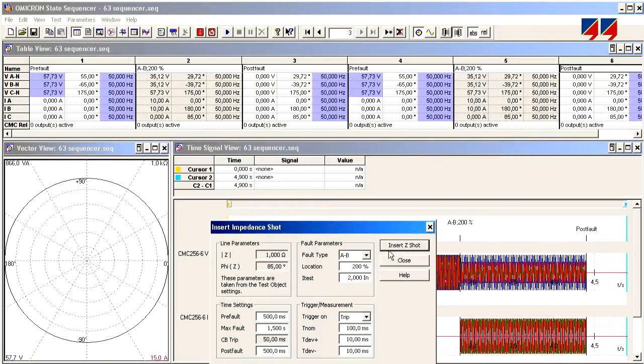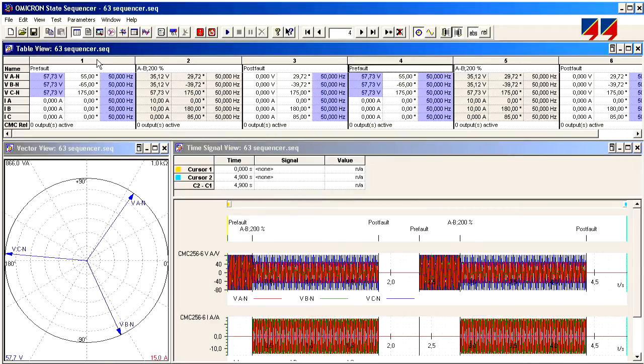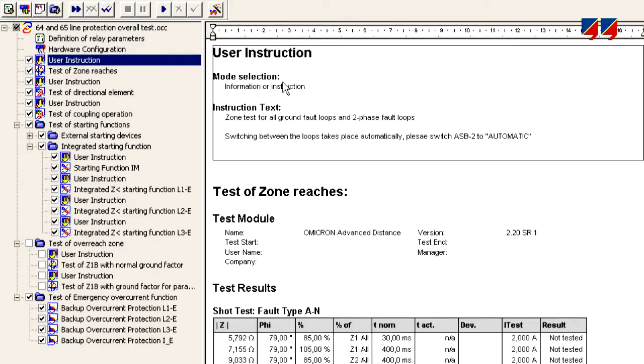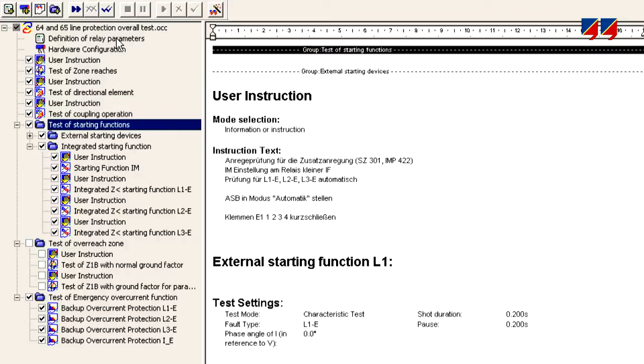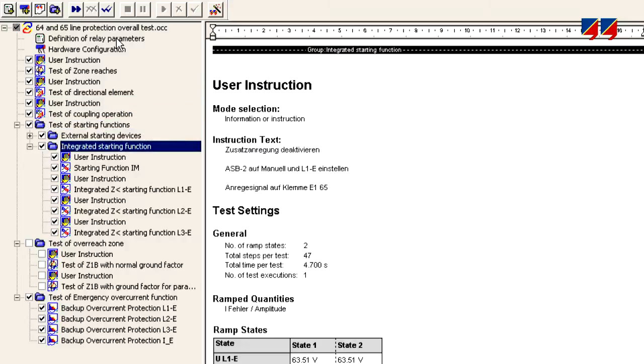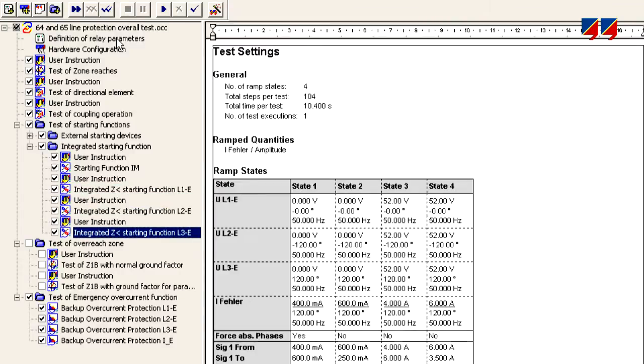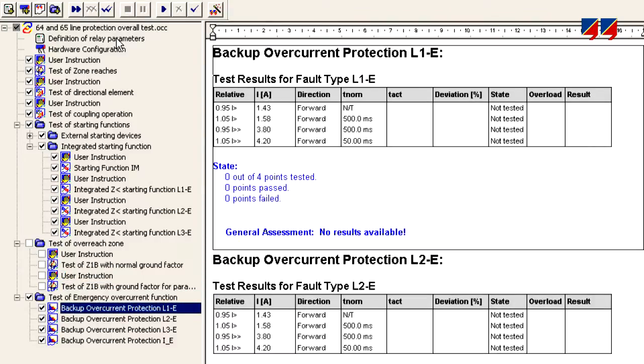The CMC also allows complete flexibility in the definition and output of dynamic sequences of test quantities, thus enabling users to create testing procedures in line with their existing preferred methods. In order to allow the testing of the many elements of a multifunctional relay using a single device, the CMC allows the combination of individual tests into an overall test plan to comprehensively cover all aspects of the relay under test.